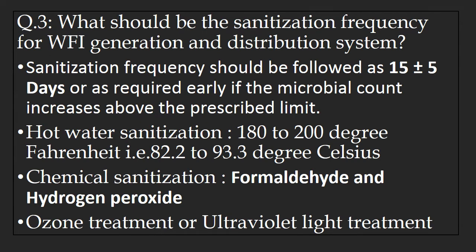Question number 3: What should be the sanitation frequency for a WFI generation and distribution system? Sanitation frequency shall be followed as 15 ± 5 days, or earlier if the microbial count increases above the prescribed limit. Most commonly, three sanitation techniques are followed for WFI generation and distribution systems: hot water sanitation, chemical sanitation, and other treatments like ozone treatment and ultraviolet light treatment.